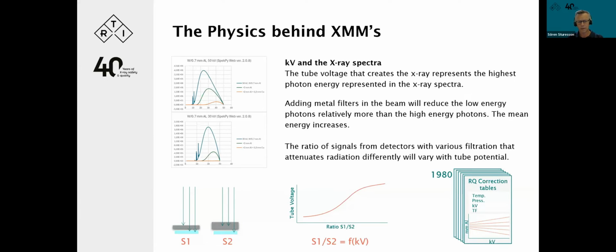But this also led to only having 2 detectors. You had one ratio, and you could read the kV if nothing else is varied. But if other things are varied, one had to use what I said, the book of corrections. If the filtration is not the filtration it was when it was calibrated, one needs to apply corrections. And that was how it worked.